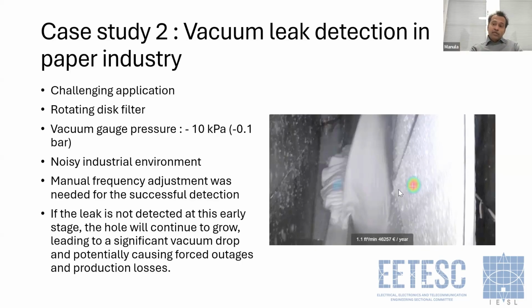Yes, it is very important to detect this kind of leak at its early stage, otherwise it would cause a significant vacuum drop, thereby potentially causing forced outage and production losses. So if the maintenance engineers or the technicians can detect these kinds of small leaks at a very early stage, they have good time to plan their outages and take remedial actions.